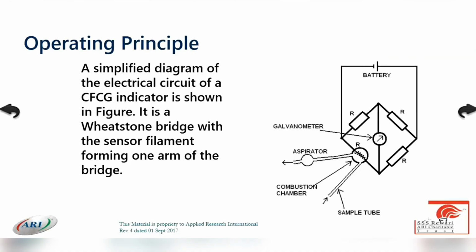The explosimeter is sensitive, the tank scope is not. The type of filament used in the explosimeter is the catalyst type, whereas in the tank scope it is non-catalyst. The explosimeter measures gases when the hydrocarbon percentage is less than the lower flammable limit. The tank scope measures gases when the hydrocarbon percentage is more than the flammable limit.